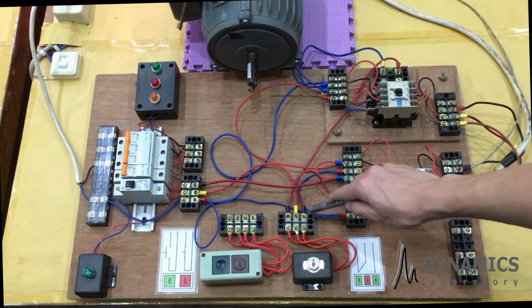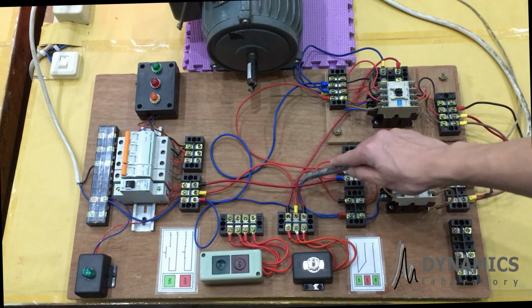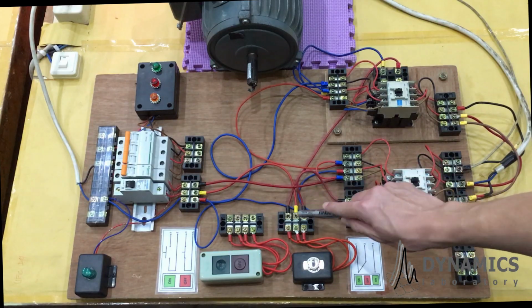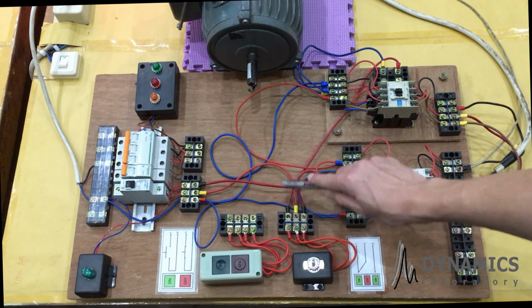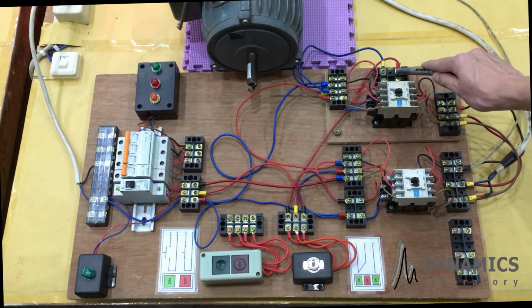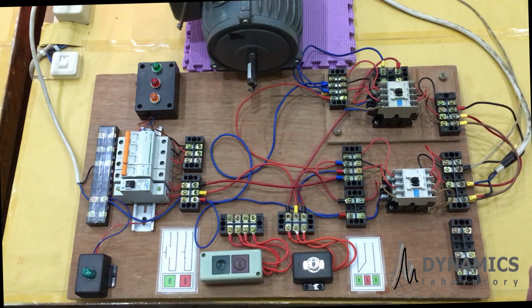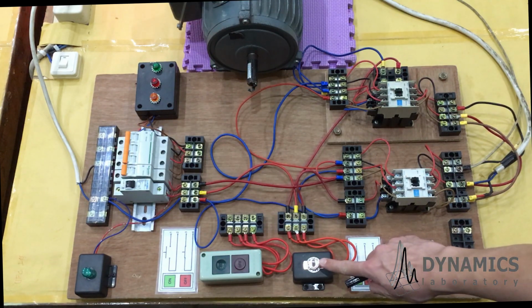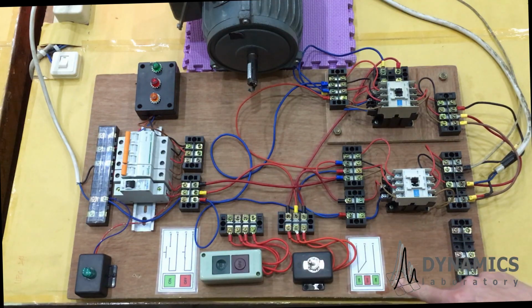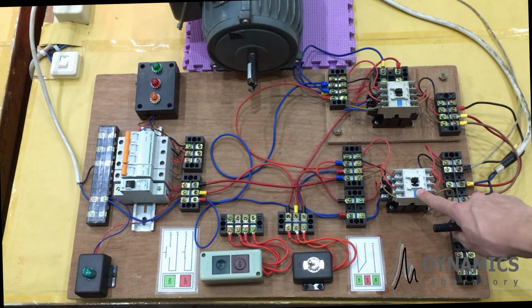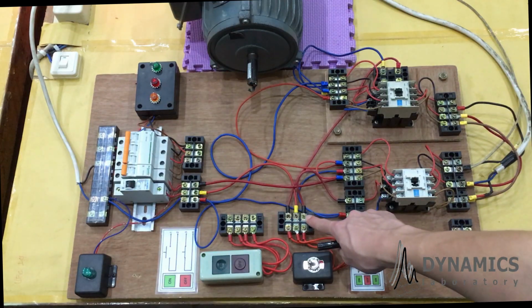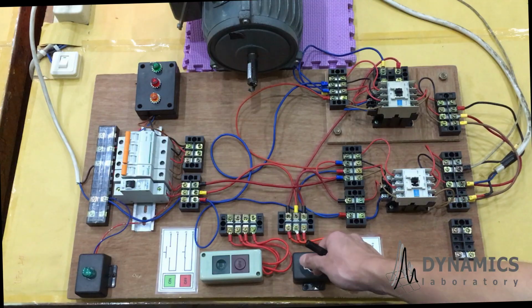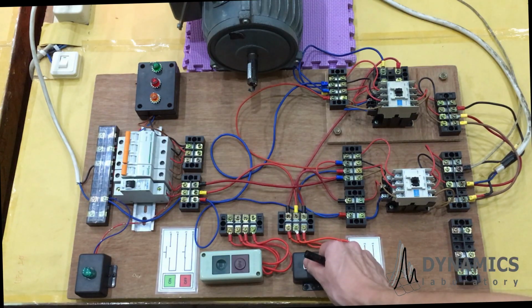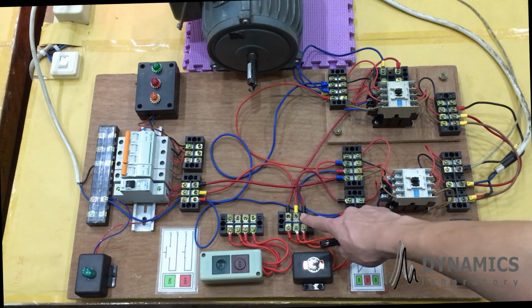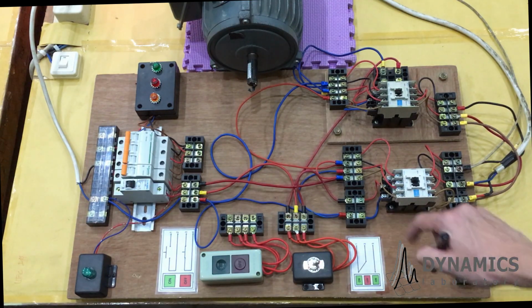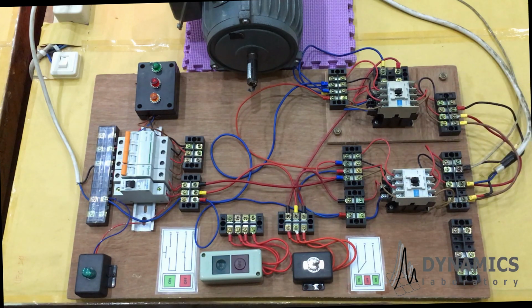From the switch control circuit, you see right leg of the switch connected to contactor 1. Meanwhile, left leg of the switch is connected to contactor 2. Therefore, as we have already proved before, if the lever position is to the left, then contactor 1 is on, because middle leg and right leg of the switch are connected. Meanwhile, if the lever position is to the right, then middle leg and left leg are connected. That's why contactor 2 is on.